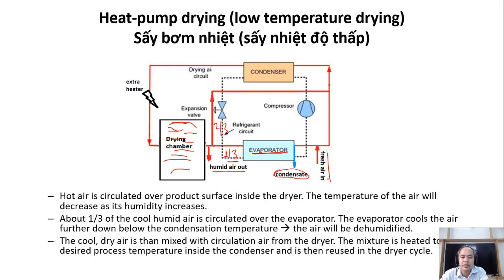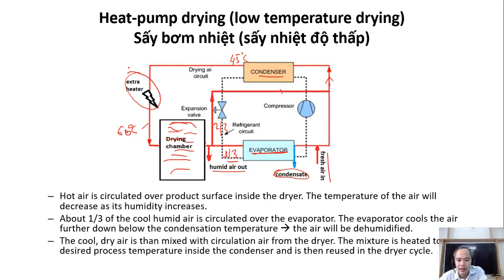After condensation, some fresh air from the surroundings is introduced and mixed with the processed air, then brought through the condenser to increase the temperature. If you want to dry faster and set the temperature to 60°C or 55°C, you may need an extra heater, because the heat from the condenser alone may not be sufficient to reach that high temperature.